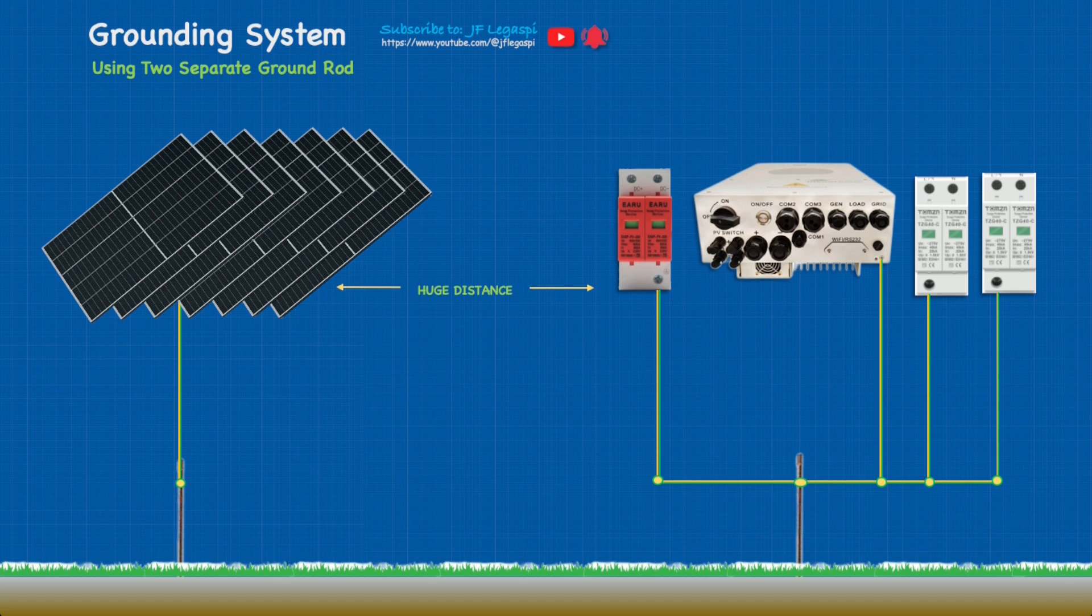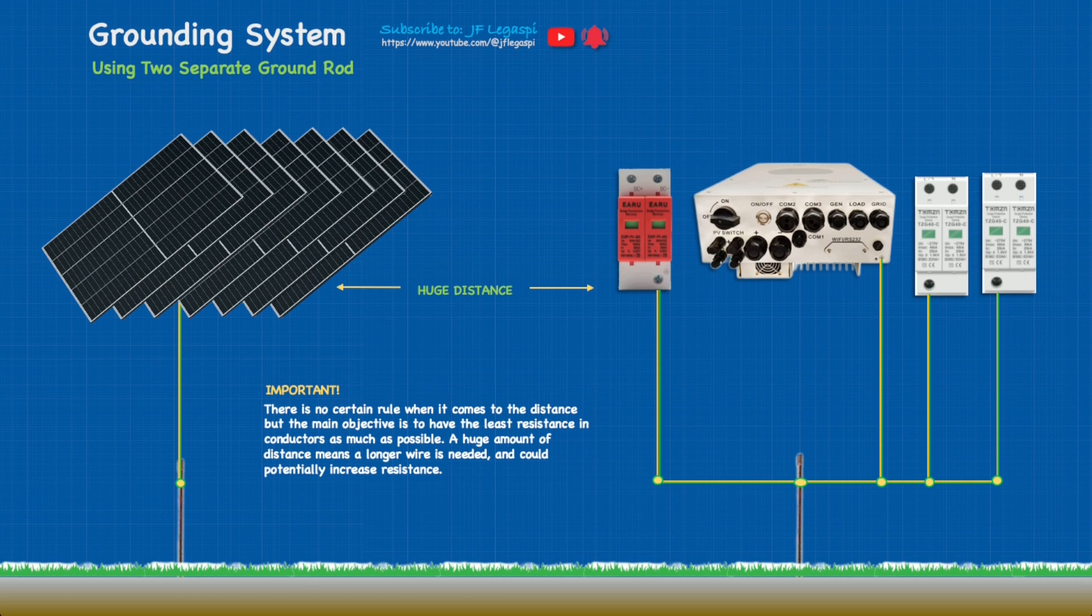Connect your PV array on that first ground rod and the main system on the second one. Important thing: there is no certain rule when it comes to the distance, but the main objective is to have the least resistance in conductors as much as possible. A huge amount of distance means a longer wire is needed and could potentially increase resistance.